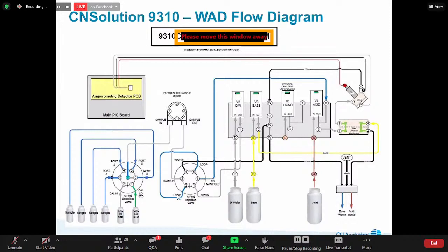When the instrument is ready to analyze the sample, the valve rotates. Then DI water, which is used as the carrier, pushes the sample into this path where it comes in contact with whichever reagent we need to react it with. Most commonly, that would be acid, which would be the first one. If necessary, we can populate this with a valve to inject ligand as well. And then finally, this flows again, as we've seen, across the bottom of the gas diffusion membrane. The base valve turns on, keeps the flow of sodium hydroxide across the top, and then that sweeps it up into the amperometric flow cell and ultimately to waste.